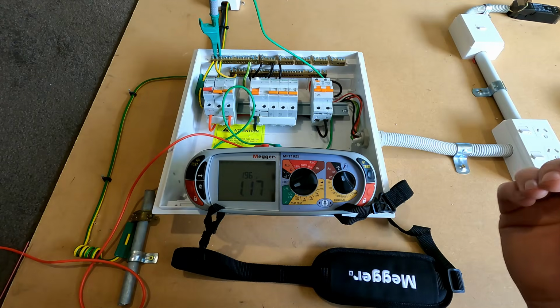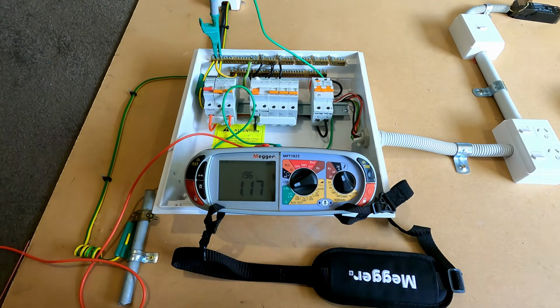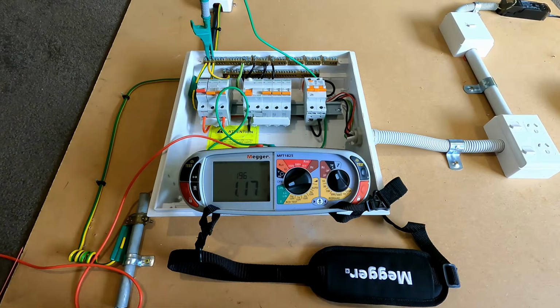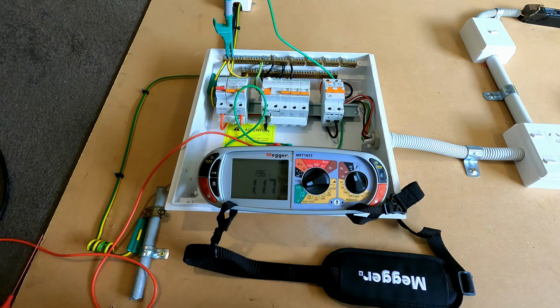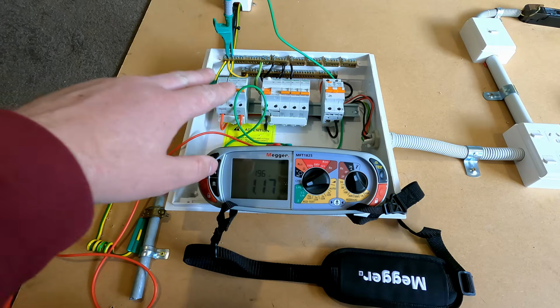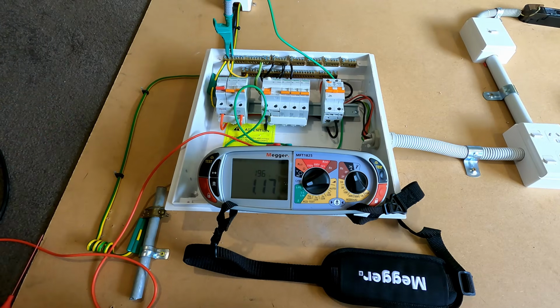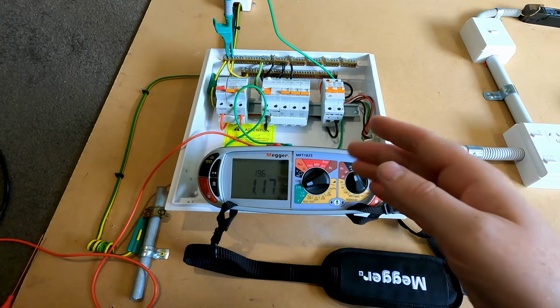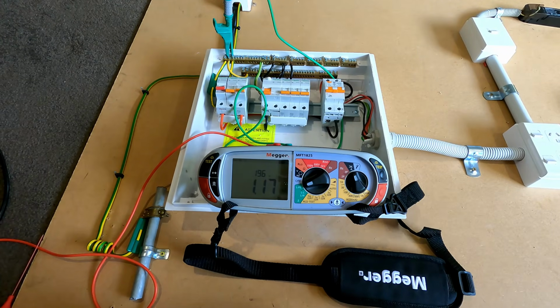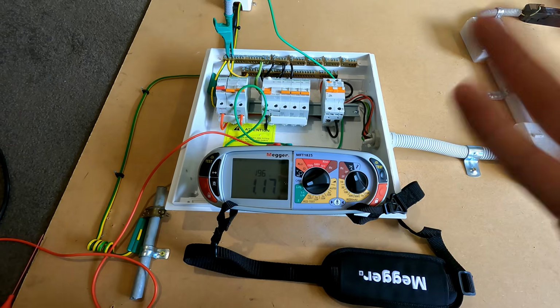Just so you guys are aware, with this installation plugged in to this cable, the impedance reading is quite high. This lead I've got it running off is probably a good 50 meters from the main switchboard. It does go back through a DB into the main switchboard. The MEN link in here is just for demonstration. As a distribution board, you would only have the MEN link in if it had a separate main earth, but that's expected because of our distance.